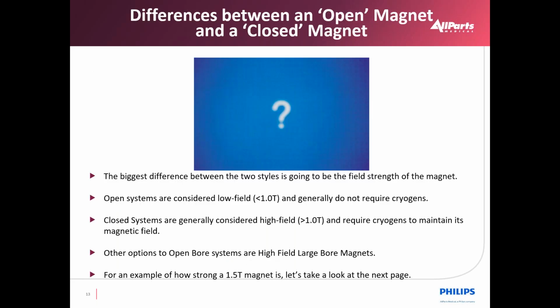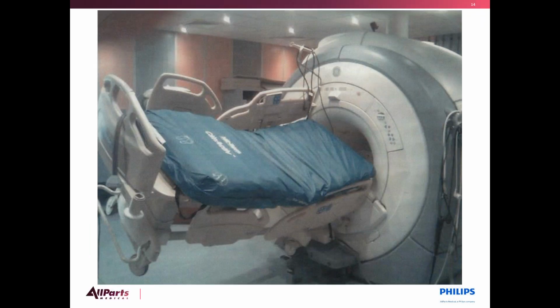While there are examples of open-bore magnets with field strengths up to 1 Tesla, they are generally considered low-field systems, and most do not require cryogens. High-field magnets are 1.5 T or greater and require cryogens to maintain the superconductive magnetic field. An example of the strength of these magnets is shown on the next slide. This is a patient bed that is stuck to a high-field MRI.